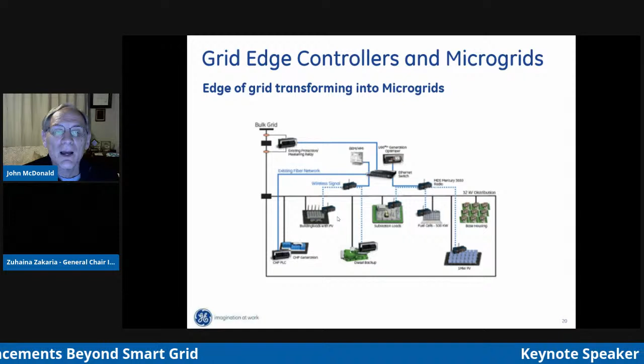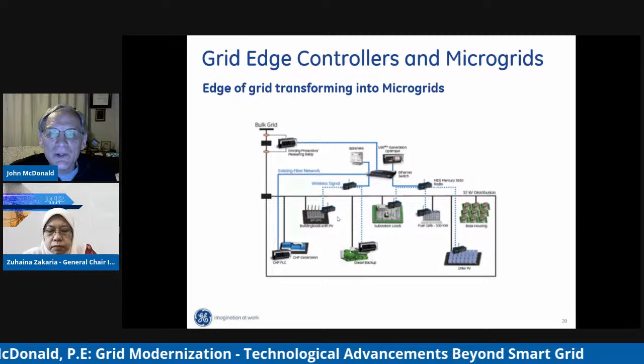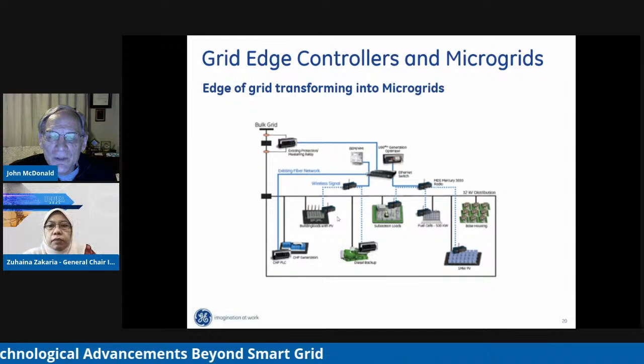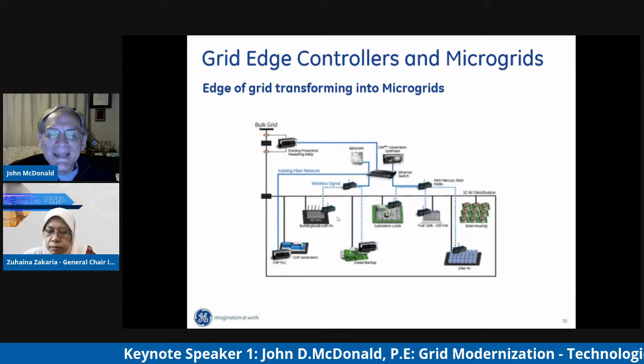So companies have developed low voltage power electronics, what we call low voltage network dynamic grid edge controllers. By dynamic, we mean continuous set point control, at the edge of grid, transforming into microgrids. These are grid edge controllers. The reason is the volatility, because of the intermittency of the sun, creates tremendous volatility on the low voltage network, and we need to mitigate that with these continuous set point controllers.